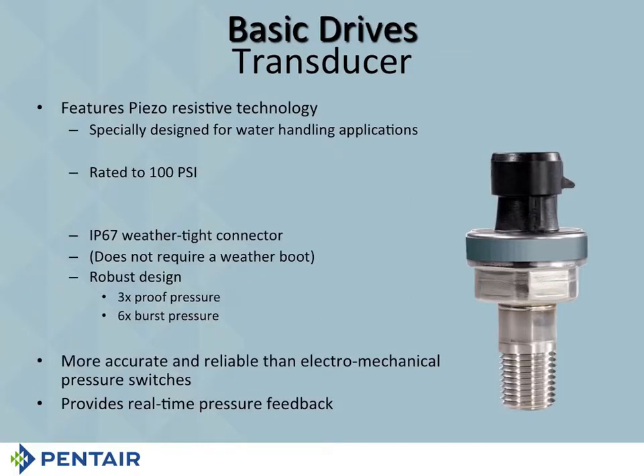Now, when you look at this transducer, I'm going to point out a section of it here. It is rated at 100 pounds. Now, the drive itself can accept up to a 300-pound transducer, but the problem is you're changing the meaning of 4 to 20 milliamps if you change out the transducer. So unless you've got a job where you require more pressure, a 100-pound transducer is sufficient.